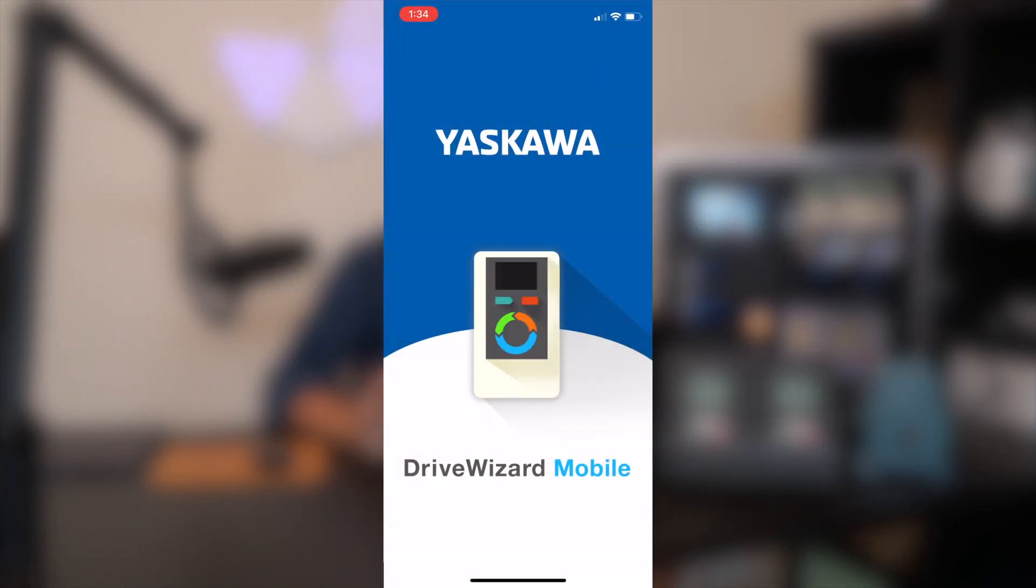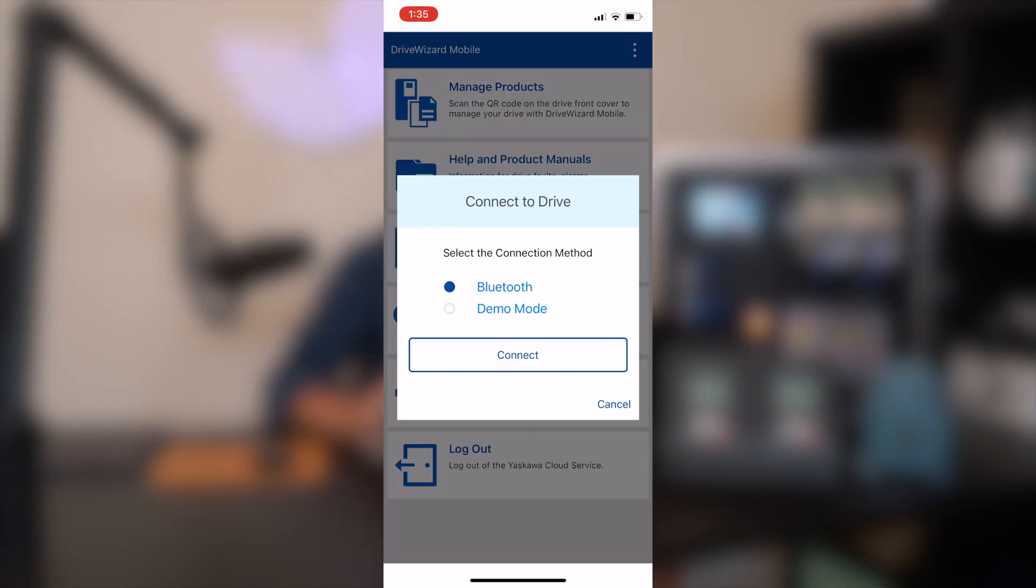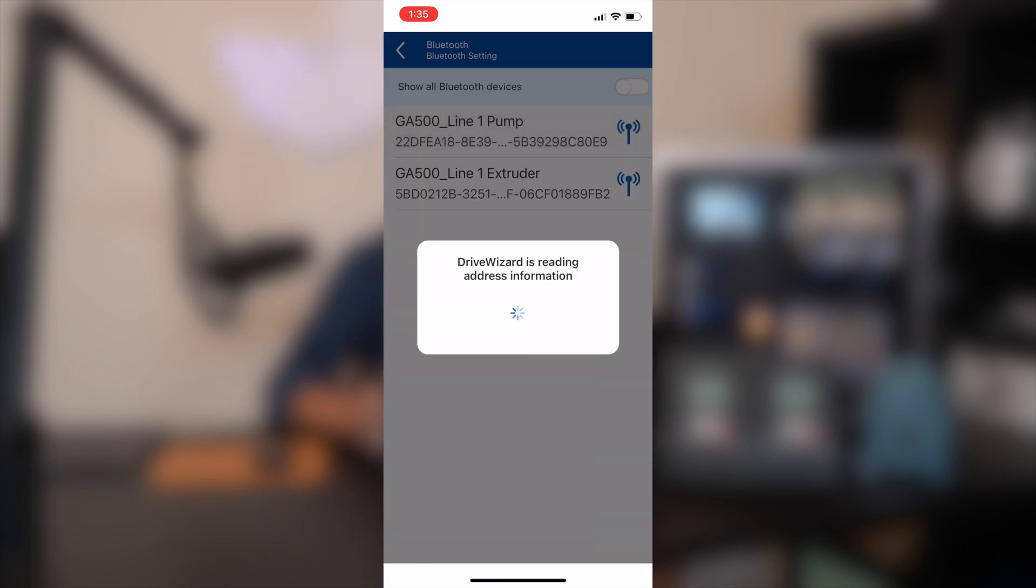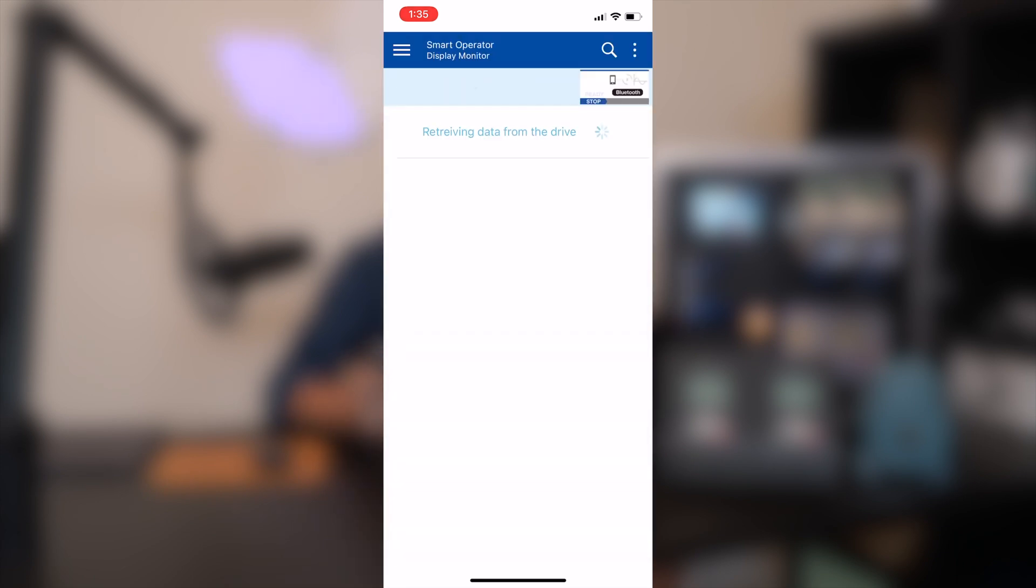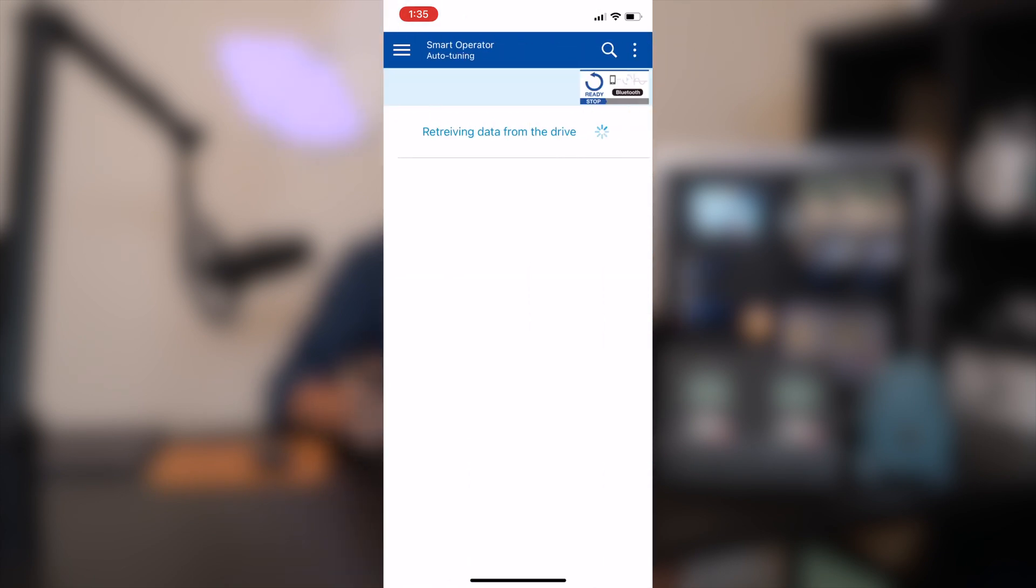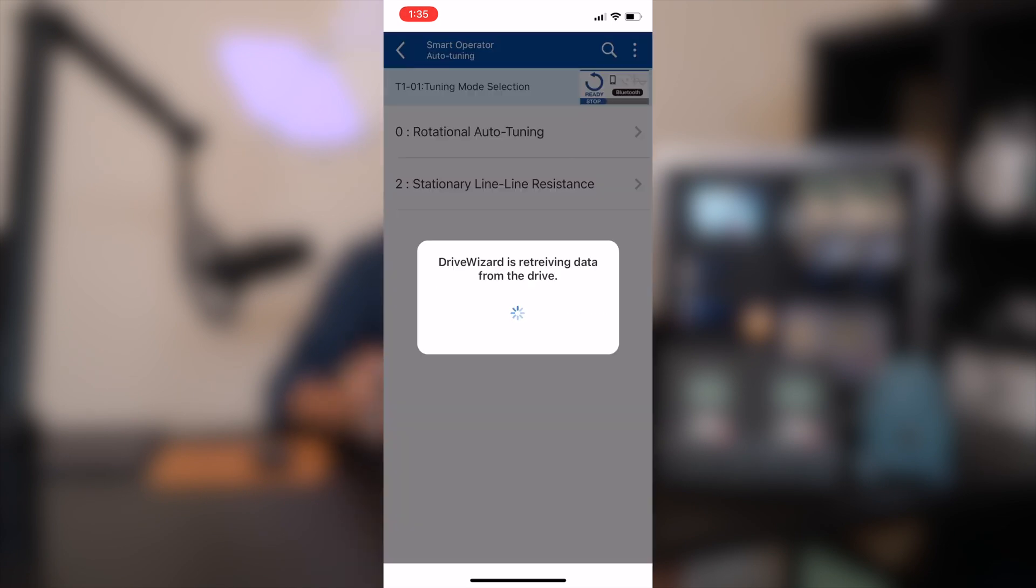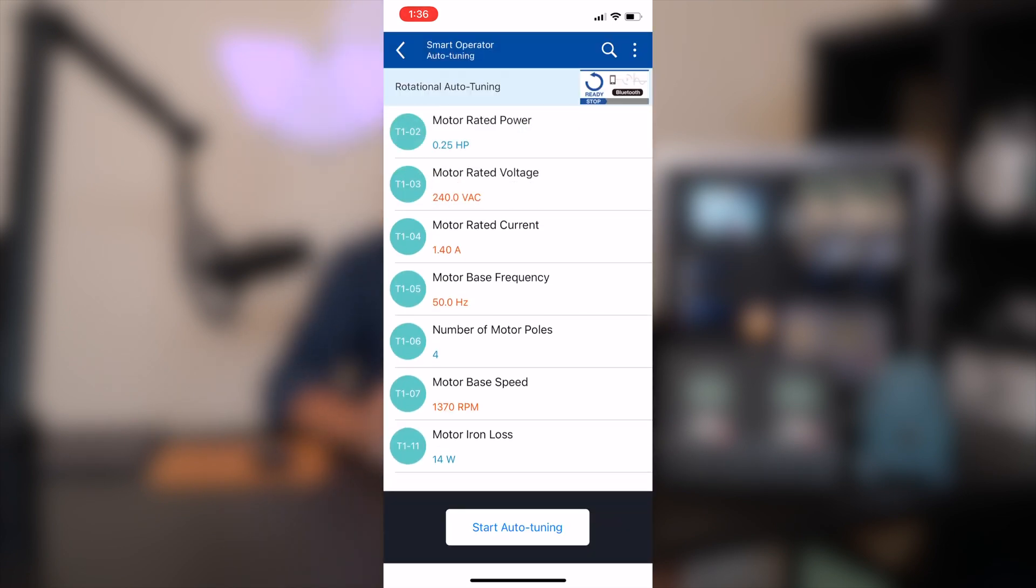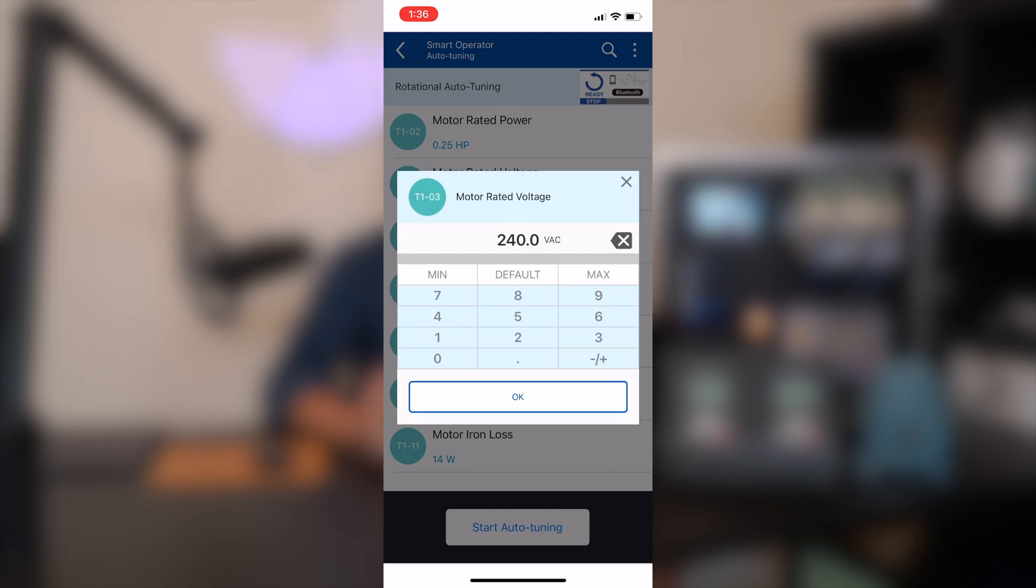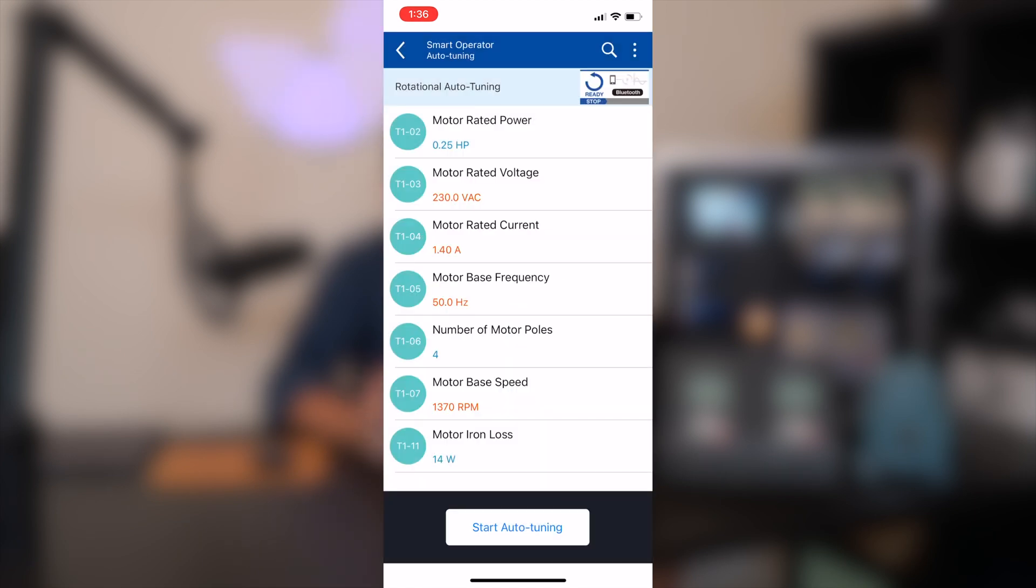One of these drives is connected to a motor, so the first thing that I'm going to do is connect over Bluetooth with my phone and run an auto-tune through the app, since it's a quick and easy way to get some parameters on the drive. One cool thing to note when we're connecting over Bluetooth is that you can customize the name of the drive and the Bluetooth settings so that you can tell them apart within the app. Now that I'm connected over Bluetooth, I'll select the type of tune that I want to run, then I'll enter the motor nameplate data and start the tune.